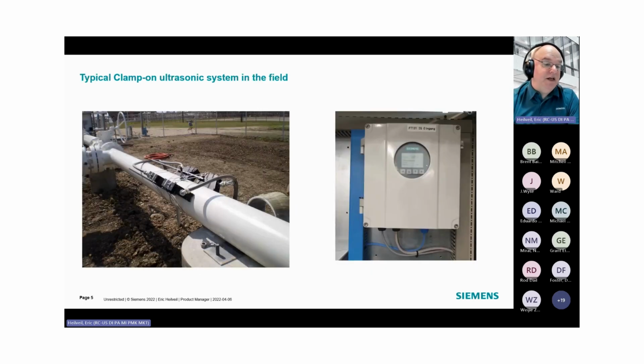Now, a typical field installation looks something like this. This is a dual beam where you have two sets of transducers on a pipe. This is a very popular natural gas or oil or petroleum type application. And then the signals are all run in the conduit, either flexible or hard pipe, and then they're run over to the transmitter over here. So basically, that's all that's required. No drilling, just some straps on the pipe. Sometimes you can just use magnets if it's a temporary install.